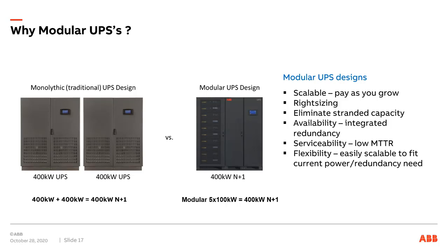And that's where the modular UPS comes in. One frame with space for smaller power modules is also what we refer to as a scalable solution. You can put in the frame, in the same picture as I used before, this is a 500 kW ABB UPS module fully populated like this. It would support 500 kW, but as there's space for 5 times 100, it will also support 400 kW with N+1 redundancy.